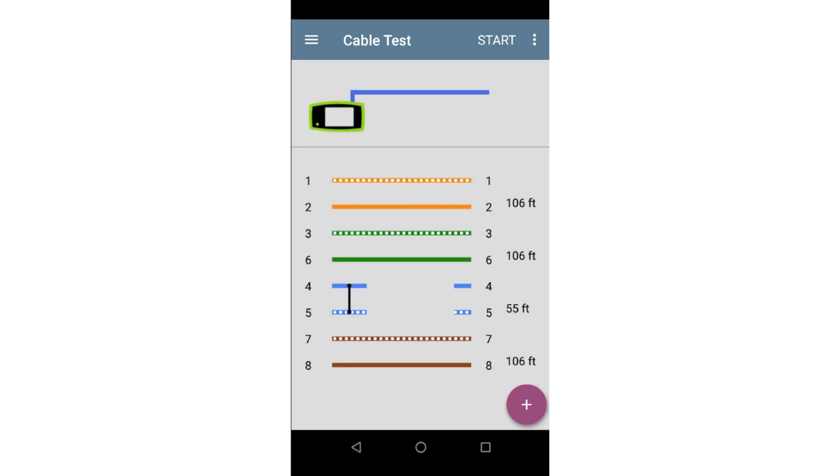Next is a case where there is a short in the cable. Here we can see three of the pairs are 106 feet long and pair 4-5 is shorted at 55 feet. Based on this, we know that something has gone wrong 55 feet from the unit.